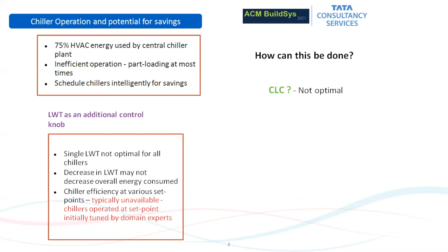So, how can this be done? Cooling load-based control is suboptimal as it does not consider individual chiller efficiencies at varying loads. Model-based predictive control is sensitive to calibration and model errors. Also, sufficient chiller data is required to develop chiller models with high accuracies.